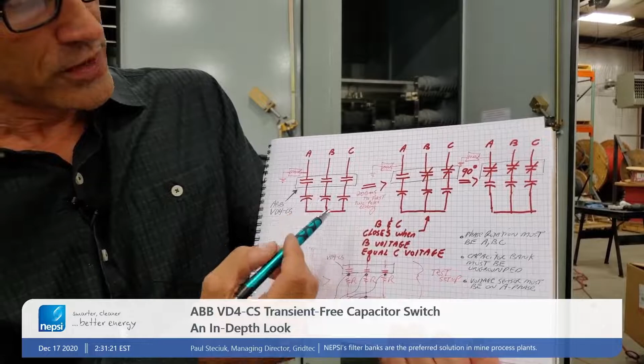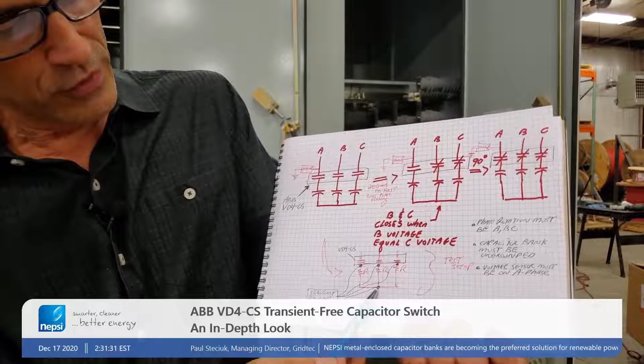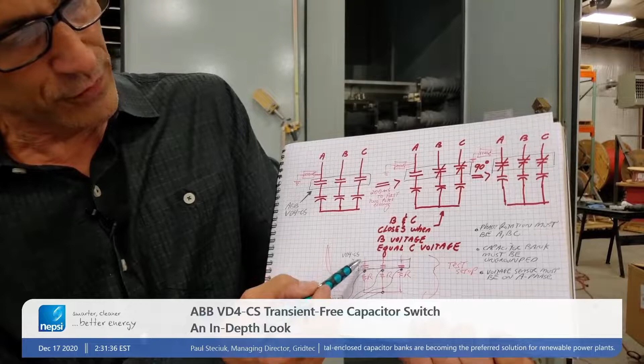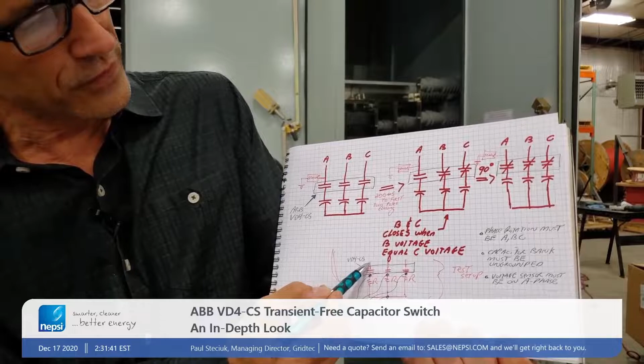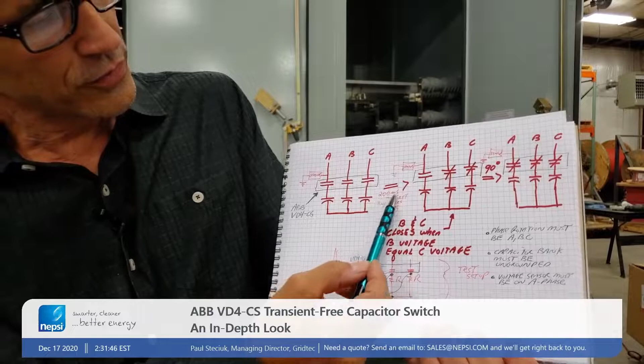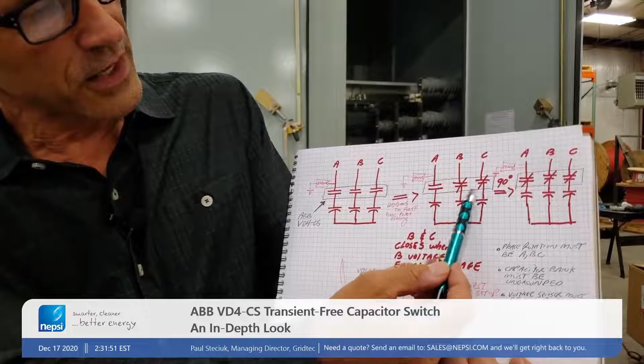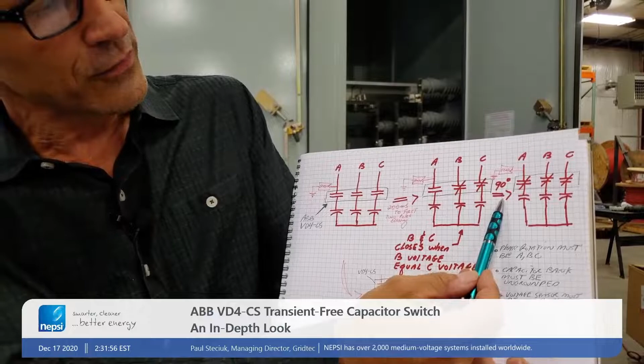The way this operates is Pete will initiate a close signal. We have voltage sensors on the load side of the VD4-CS located here and also on the neutral. So we're recording the waveforms with a transient recorder. We're injecting voltages with a 3-phase voltage source on the line side of the VD4-CS. So the way it works is that when we send a close signal, 200 milliseconds later, we'll see that the phase B and phase C contacts close. We're going to see that on the transient recorder. And then 90 degrees later, we're going to see phase A close. So this is interesting to watch.